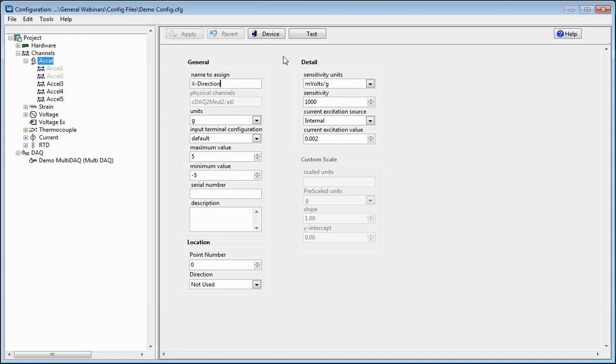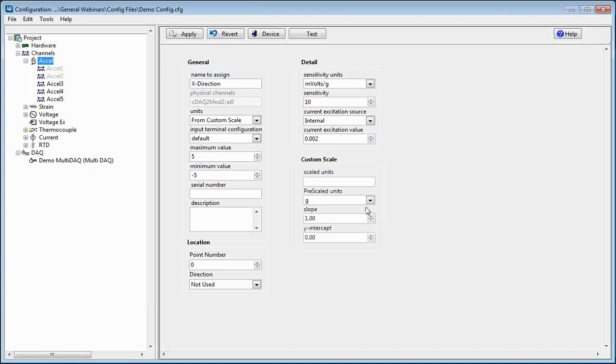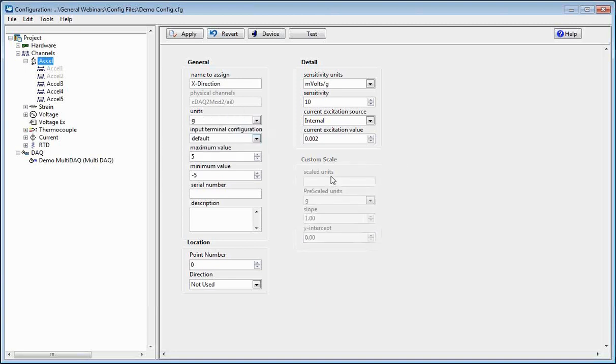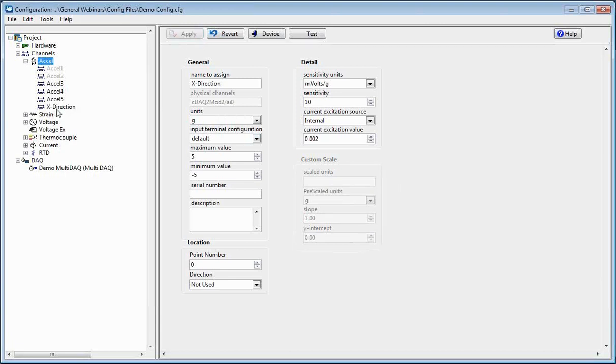Let's call this 'X-direction' as the name of the accelerometer. You can give it units — particularly Gs — and then you'll want to fill out the sensitivity information. This particular accelerometer I'm using is a 10 millivolt per G sensitivity. We'll update that, choose excitation source, and if you wanted to use a custom scale, you would change your scale units to custom scale and then update what the units are, along with your slope and Y-intercept to get those units. In this case, we're going to stick with Gs. Once you've made all the changes, just click Apply and you'll see it shows up in the list of accelerometer channels.